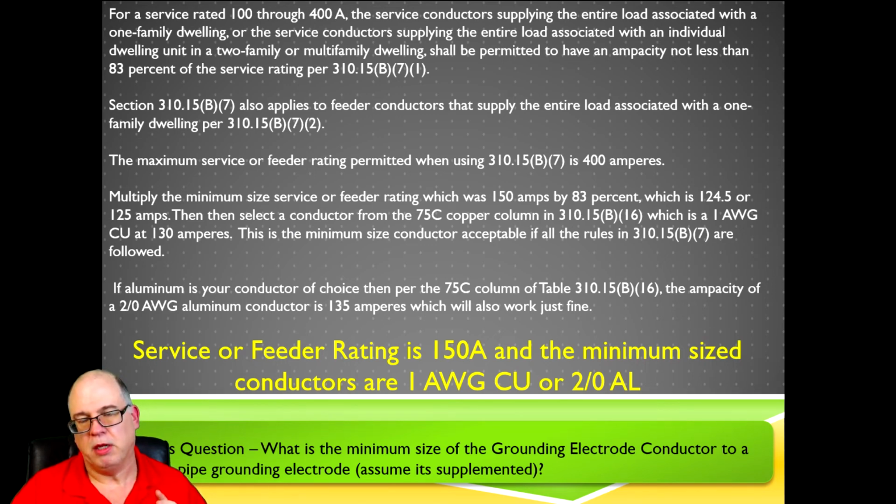Perfectly okay. Now, if you're used to doing motors and you're used to doing HVAC systems, this is not going to scare you. For many people, they look at this and go, oh my God, no, you can't do that. There's a violation. Code says you can do it, do it. It's all based on diversity. It's all good, my friends. Don't worry about it. All right, so now we got to have a conductor.